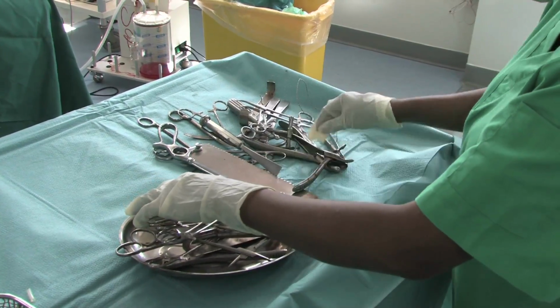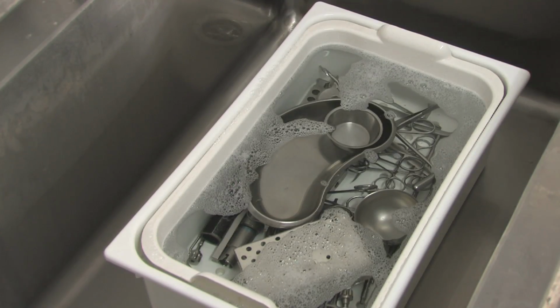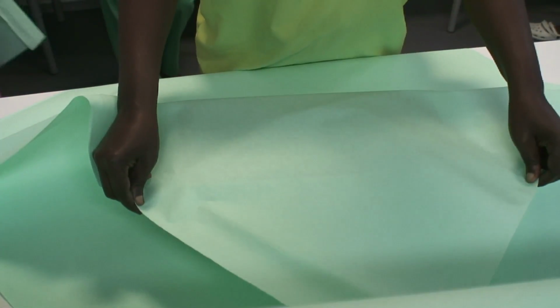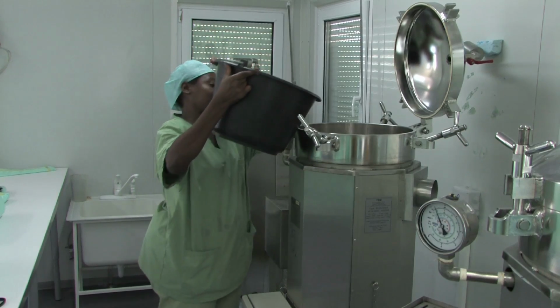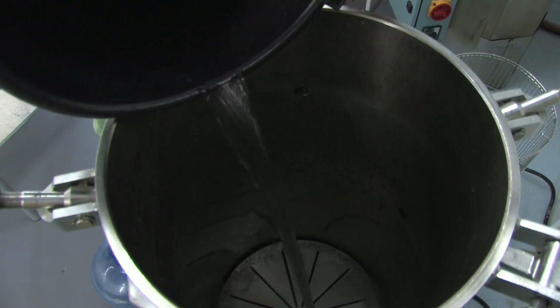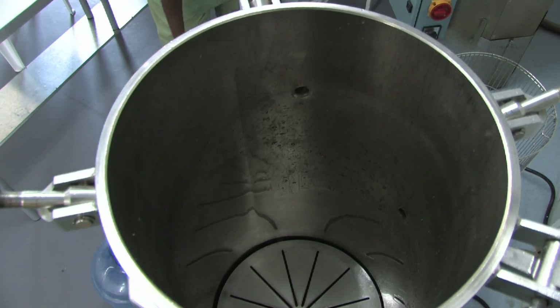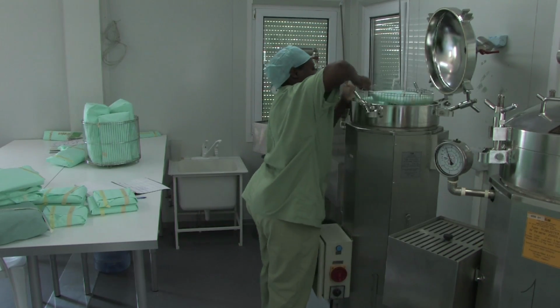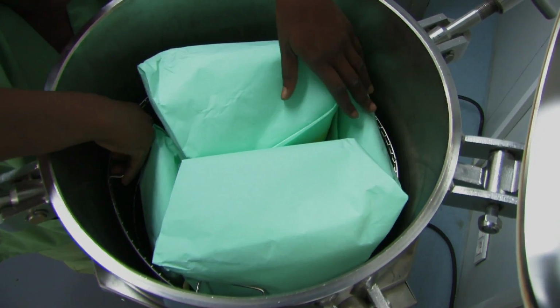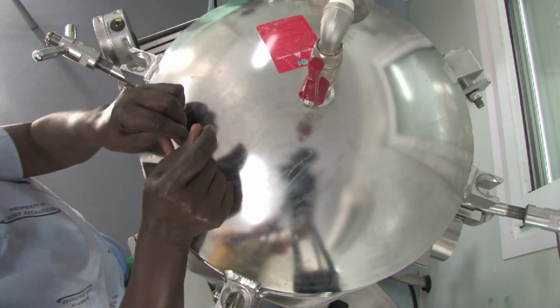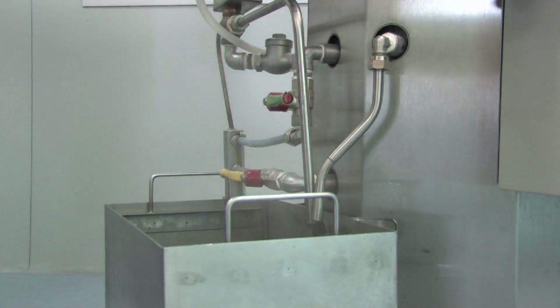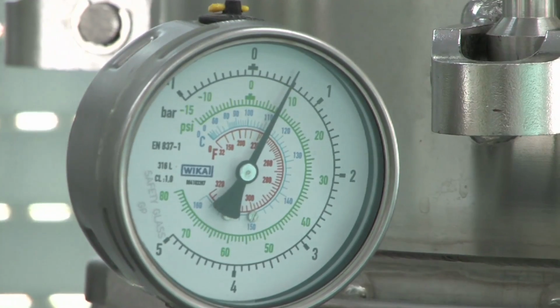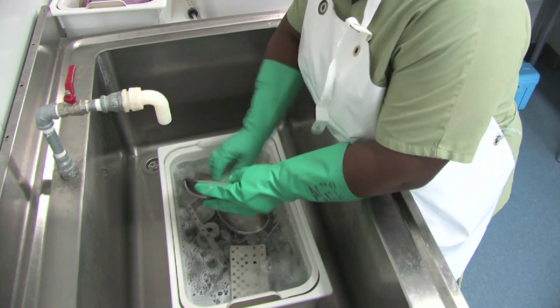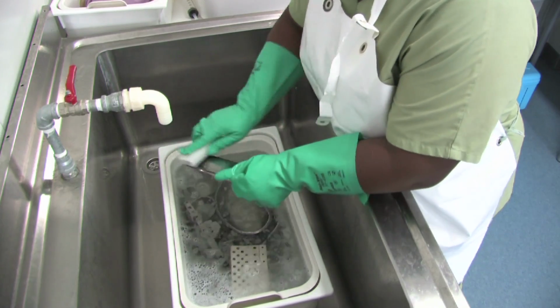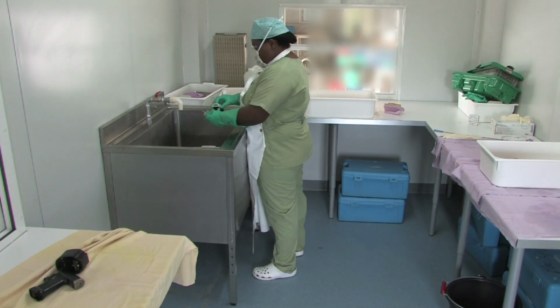Sterilization consists of destroying the germs present on medical devices and keeping the devices sterile until they're used. The sterilizing agent used at MSF projects is saturated steam. Germs are fairly resistant to steam. Every minute spent in an autoclave destroys some of the microorganisms. If there are a lot of hard-to-kill organisms on an instrument, only some of them will be destroyed, and the ones that survive can infect the next patient. That's why it's very important to reduce, as much as possible, the number of organisms present on the medical device before it ever gets to the autoclave.